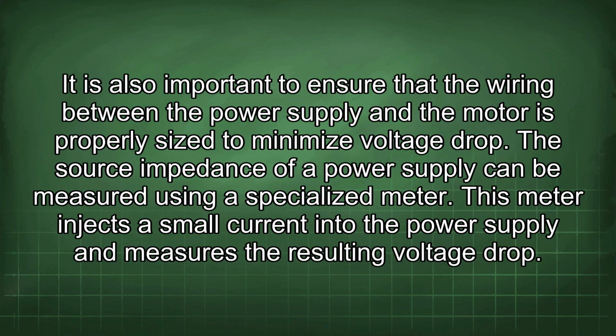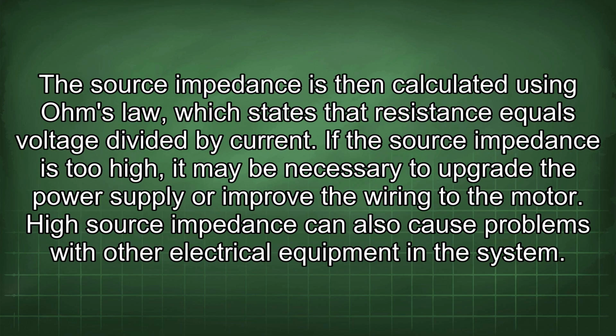motor. It is also important to ensure that the wiring between the power supply and the motor is properly sized to minimize voltage drop. The source impedance of a power supply can be measured using a specialized meter. This meter injects a small current into the power supply and measures the resulting voltage drop. The source impedance is then calculated using Ohm's law, which states that resistance equals voltage divided by current.